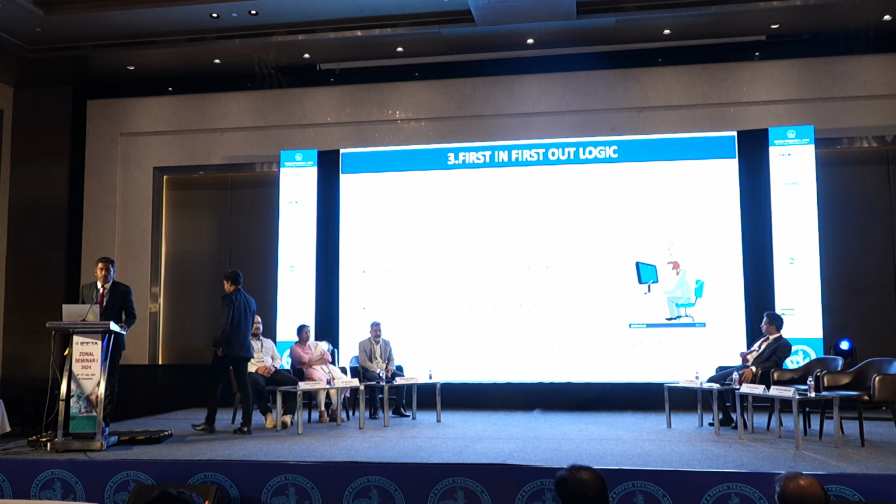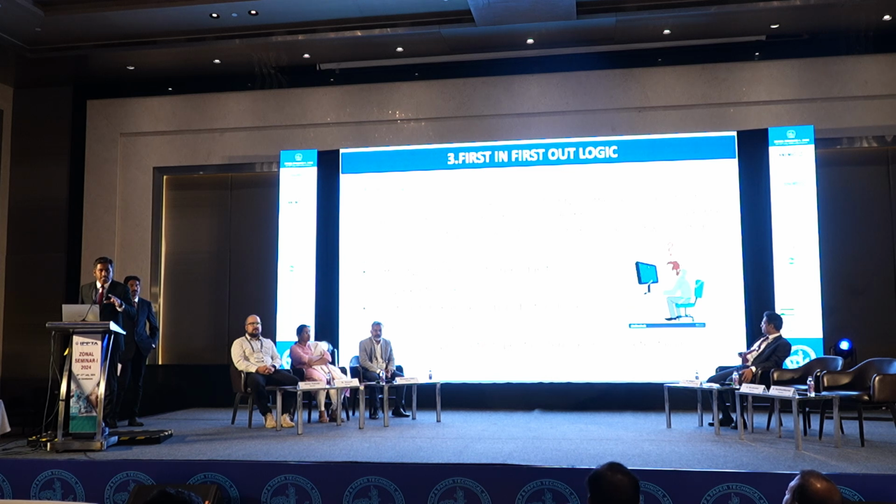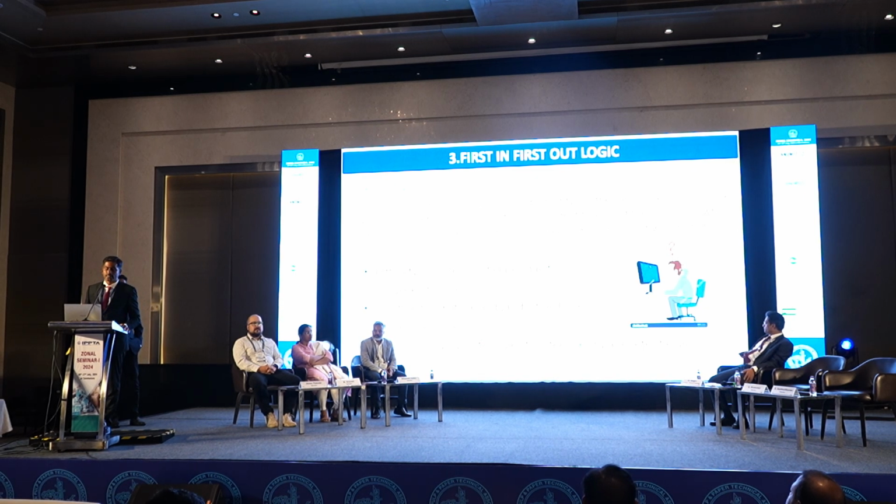To identify the particular cause, we implemented the FIFO block. We faced this during plant startup; the maintenance department knows very well how we struggle. If one pump or equipment fails, what is the reason? All the people surround me. That's the time your maintenance people struggle, and that's when we introduced the FIFO block in our DCS.